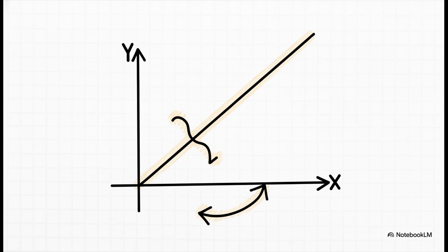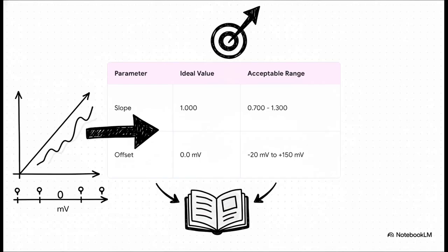The offset tells you how good your 0 point is. The slope tells you how accurately the analyzer is responding to the known concentration of your span gas. These two numbers define everything. And this table here lays it all out for you. Your goal, the perfect score, is a slope of exactly 1.0 and an offset of 0. But we live in the real world. So the manual gives you these acceptable ranges to work within. As long as you're inside these windows, you've got a successful calibration.